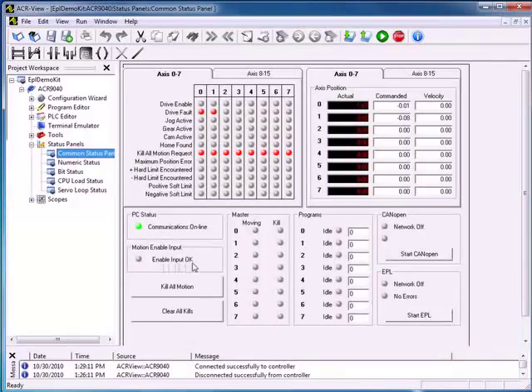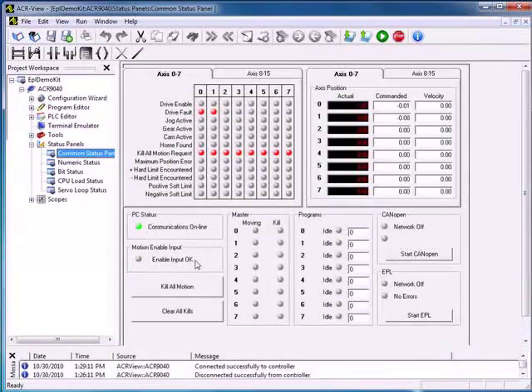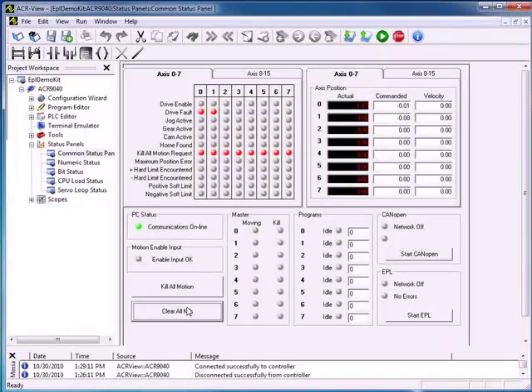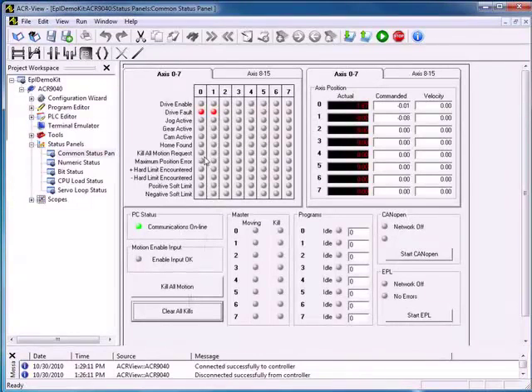From this screen we can clear all of our kill motion requests as long as there is no current error status preventing that. So let's do a clear all kills. We have no problems preventing us from clearing those, so we can see now that we no longer have a kill all motion request for our axes. This screen shows axis 0-7 by default but also displays axis 8-15, so we can see the status of all 16 axes.